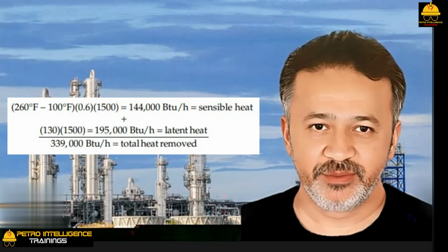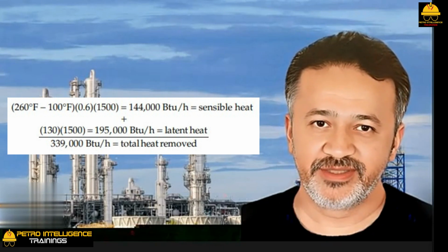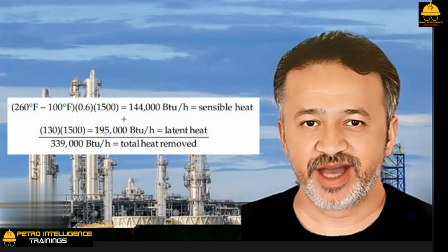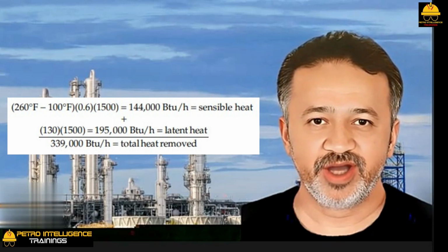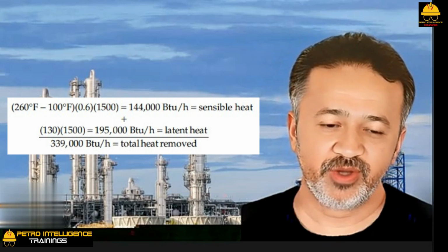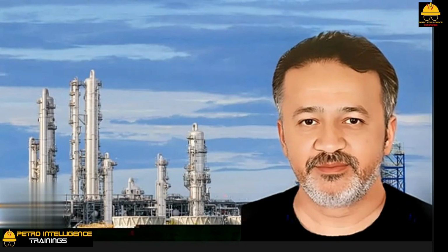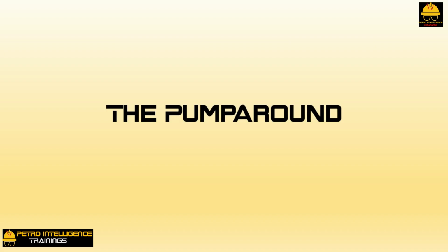260 degrees Fahrenheit minus 100 degrees Fahrenheit times 0.6 times 1500 equals 144,000 BTU per hour equals sensible heat. Plus 130 times 1500 equals 195,000 BTU per hour latent heat, equals 339,000 BTU per hour total heat removed.